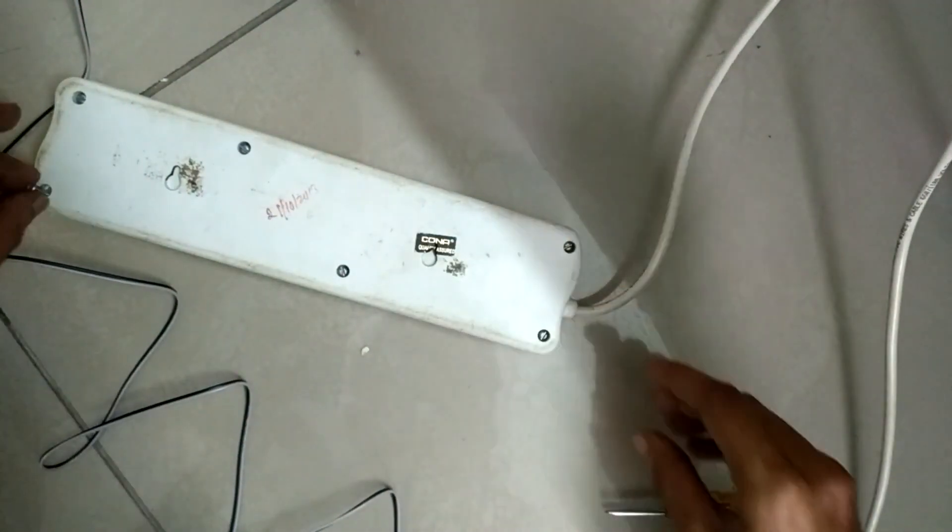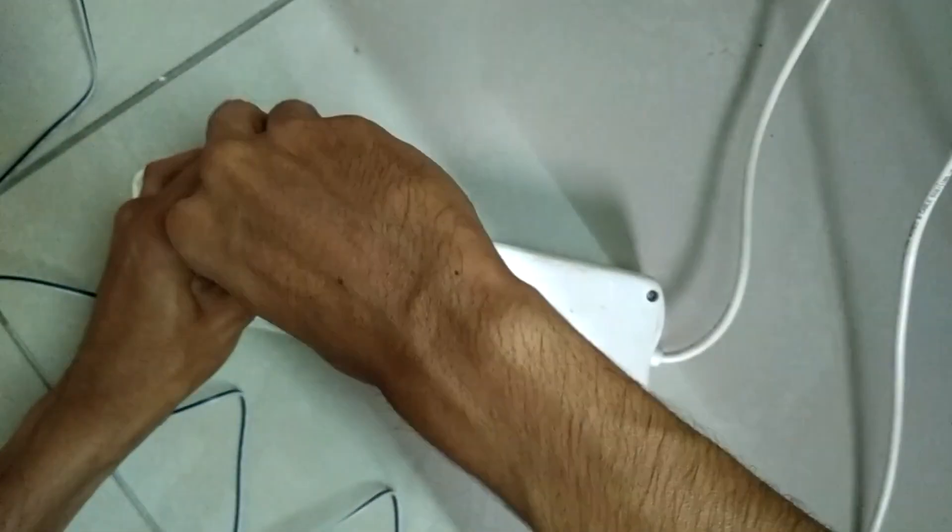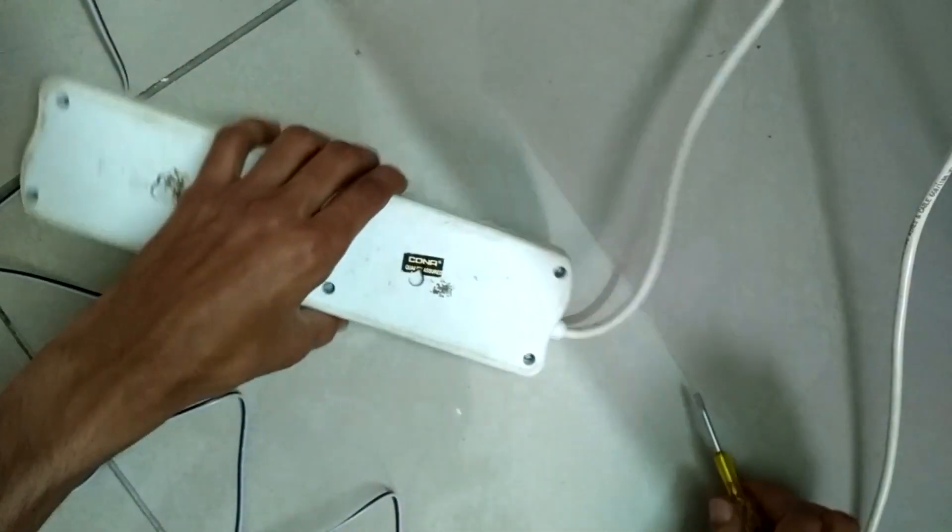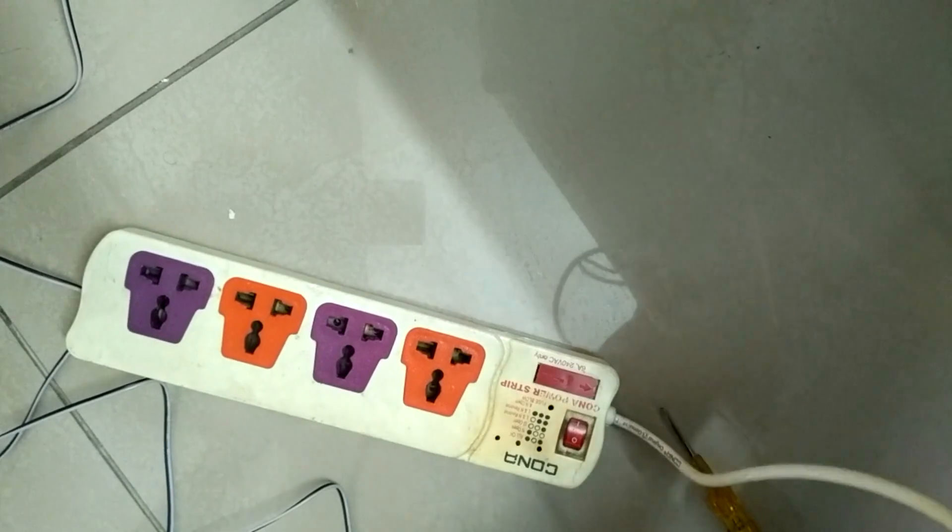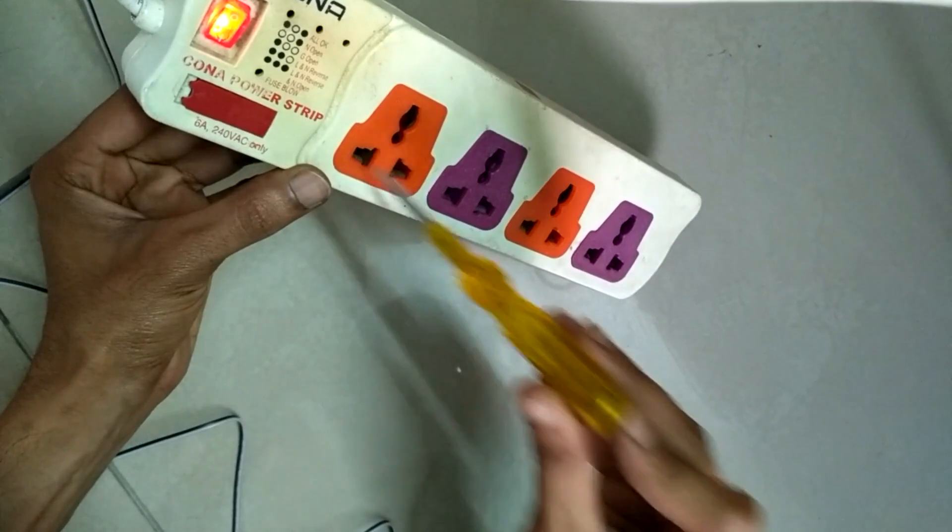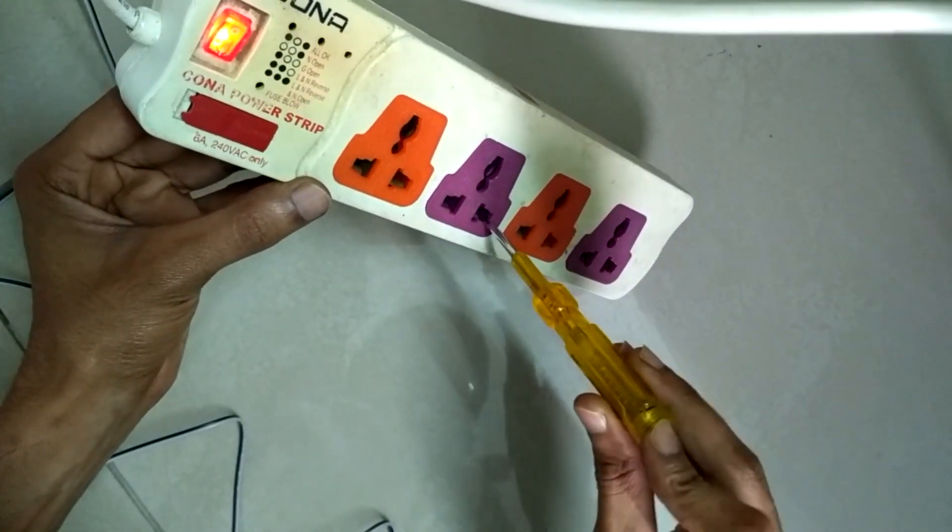Now close the back cover. Turn it, turn all the screws clockwise. Now finally check the process using the tester. Now the line comes towards right side. Left one is neutral, right one is line, top one is earth. And same to all the remaining sockets.